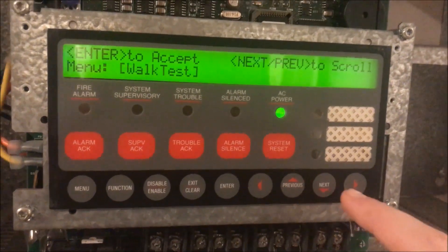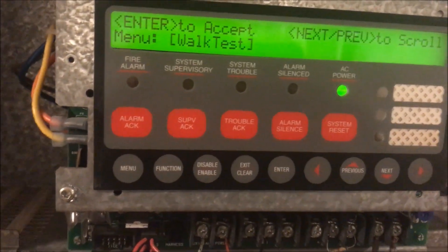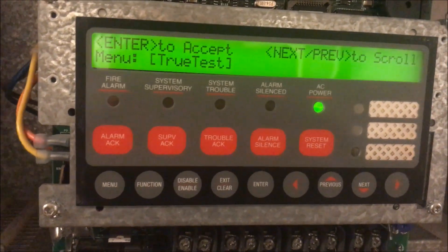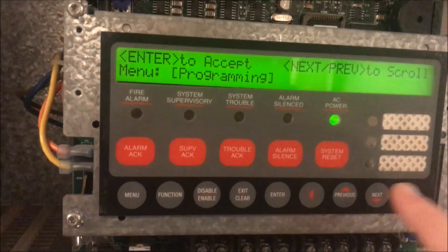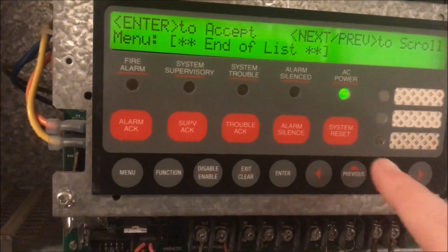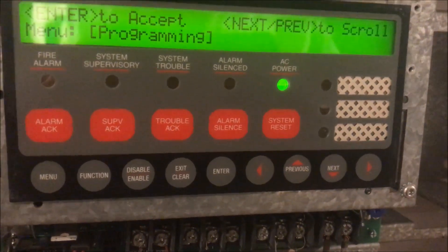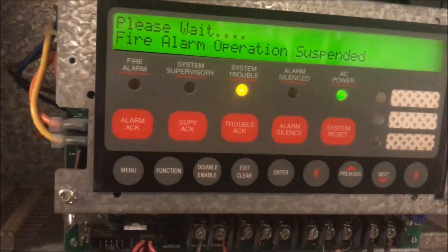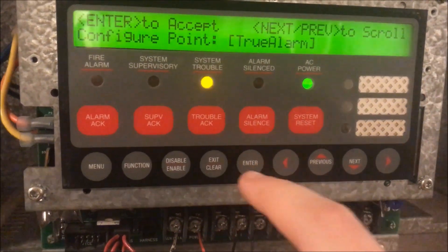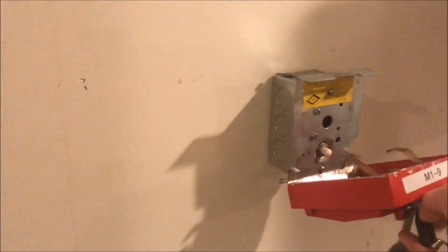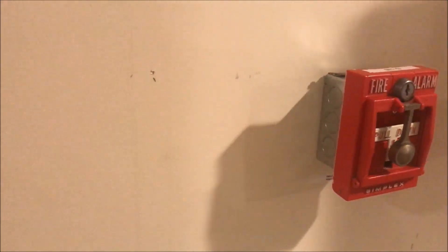Other level three features: setting a walk test, setting a true test (though I don't have the addressable alarms for that so we'll skip it for now), basic programming, and viewing reports — reports are basically what the panel is sending to the printer. If you go into programming, you're going to get a trouble condition, and at that point if any pull station or device is activated, the panel won't respond normally.